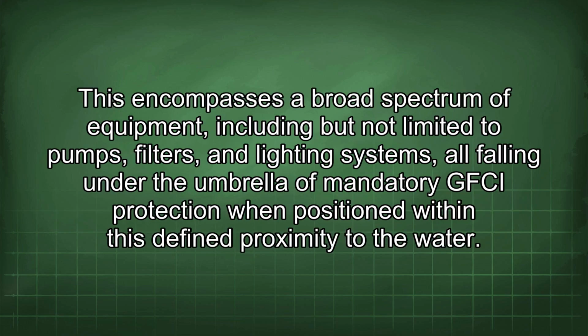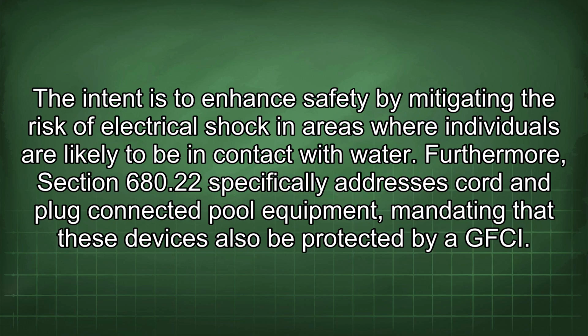This encompasses a broad spectrum of equipment, including but not limited to pumps, filters, and lighting systems, all falling under the umbrella of mandatory GFCI protection when positioned within this defined proximity to the water. The intent is to enhance safety by mitigating the risk of electrical shock in areas where individuals are likely to be in contact with water.